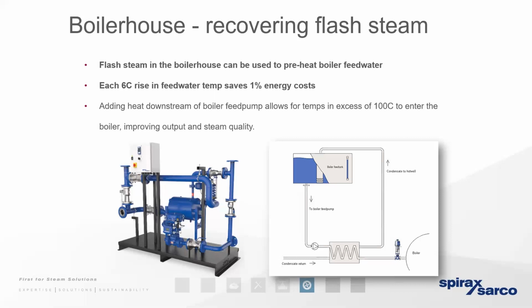So I'm thinking about laundries, the textile industry, distilleries. By no means a limited number of processes, but wherever we've got a high steam consumption pressure, that's where we expect a significant pressure drop to result in a lot of flash steam on the condensate line. And a significant payback can be enjoyed under these circumstances.